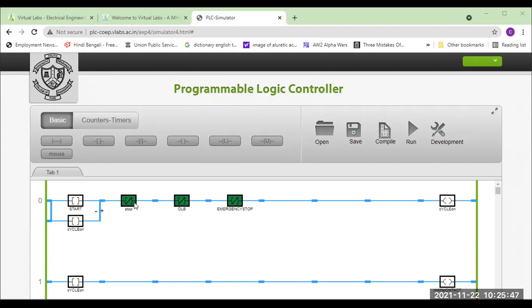So remember this, whenever action is taken on the stop button, look, here the stop button status is 1. But whenever the action is taken, it goes from the NC to the NO connection. So the NO connection will be 0, means 0 state. So it will cut this path, so that this M cycle on relay contact will not run.